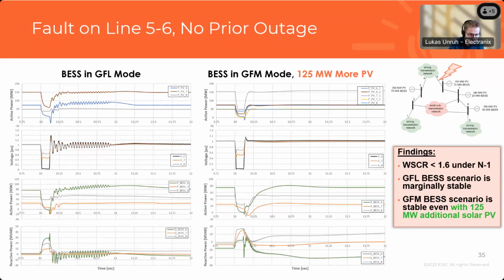These BESSes were located at different parts of the system, so in the post-fault scenario we'd expect different reactive loads, different reactive demand for the different resources throughout the system. It just depends on the post-fault topology of the network. It's different between GFL and GFM here, it's 125 megawatts more PV added in the case on the right, so the flows are going to be different as well.